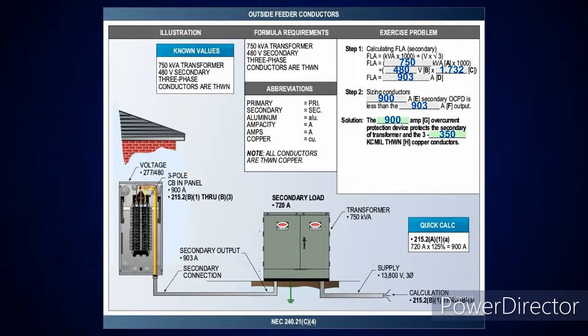I had a good time. So here's one. You'll notice there's no length here we're talking about, and these are the outside feeder conductors. I'm going outside, transformer. We even put in a new transformer, like you would see outside. We've got a 750 kVA transformer, and you look at that secondary connection. What is it? It's 480 volt, three phase, 1.732. That'll give you 831 volts. You divide that into the VA of your transformer, and it gives you 903 amps.